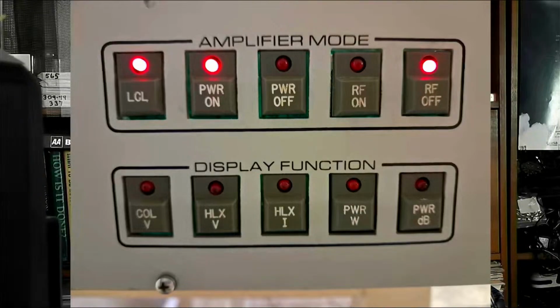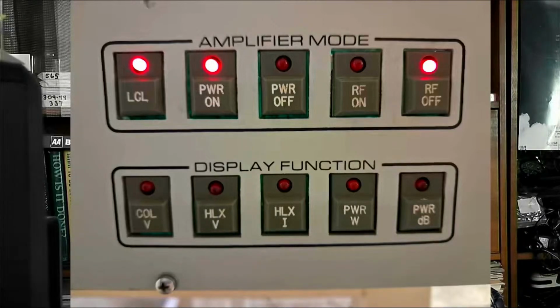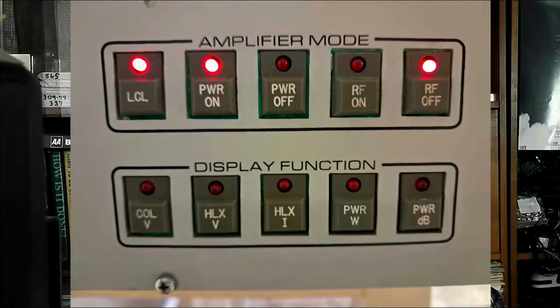When you press power on, it starts a timer, a 2-minute timer for the filament to warm up properly, and only then can you press RF on, which switches on the high voltage. Then you can press any of the buttons at the bottom to get your collector voltage, helix voltage, and helix current, and view output power in watts or dBs, probably dBm. So that's the control panel.